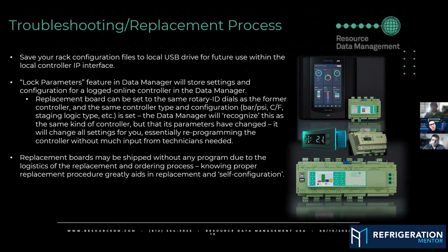So Chris, let's talk about, just say it's a case controller. Case controller, got a surge to it, fried it, or something like that. Yep. So what are the 3 things that they would need to put in? Because they'd have to power it up. You'd have to hook your computer up to that case controller. And then what are the 2 or 3 things they would have to do before they plug in the Ethernet cables? It's Cat6. Cat6. So before they plug into Cat6, what are the 3 or 4 things they need to do on the computer again? On a case controller, there is, I think, literally 3 things they need to do.